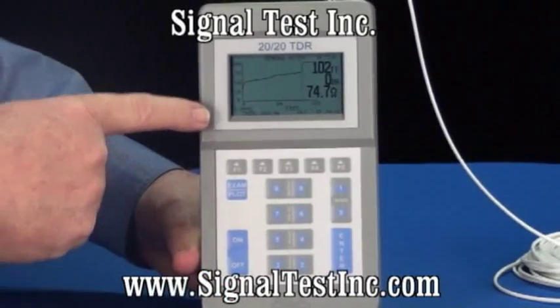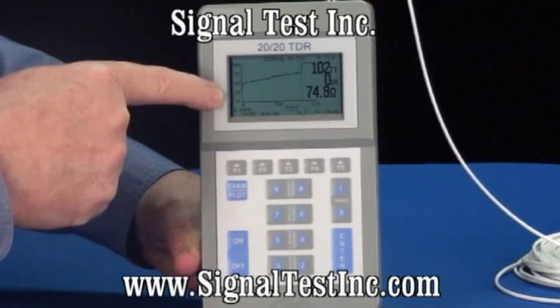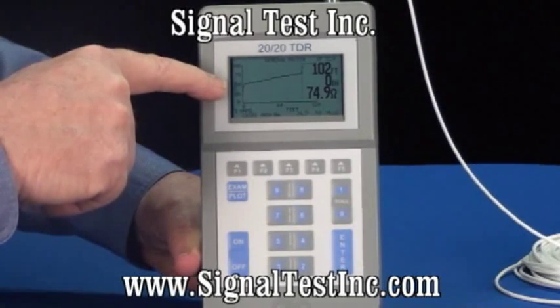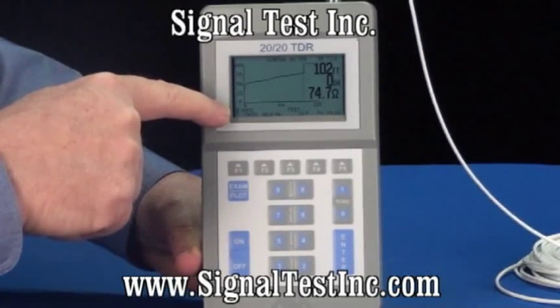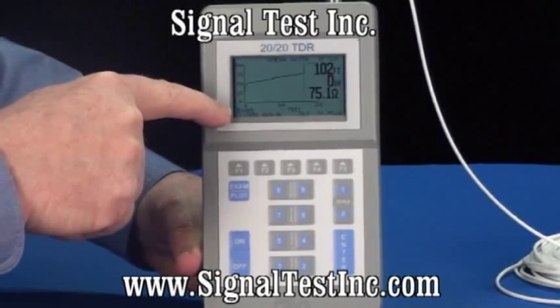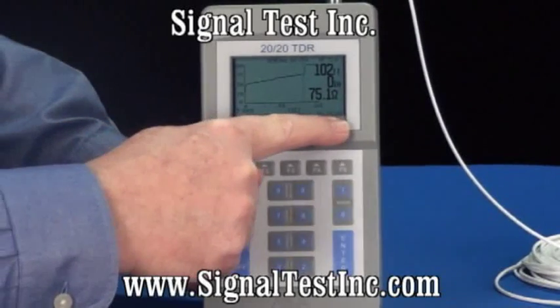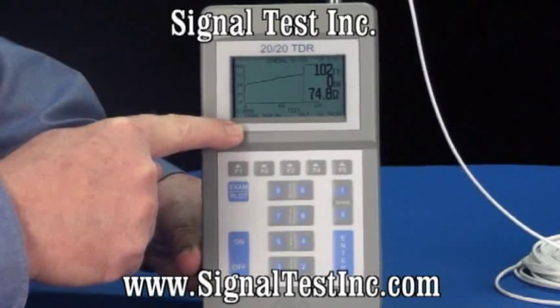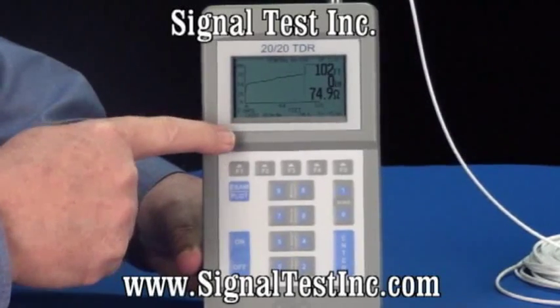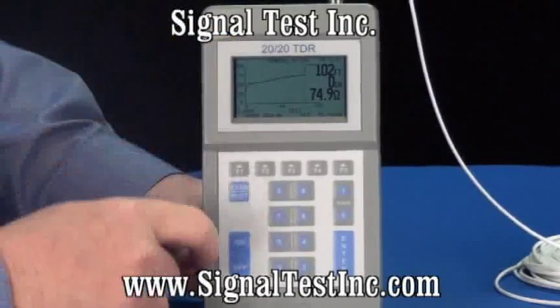Now on the measurement screen we have a scale from 0 to 100 ohms. The cable starts out at 50 ohms and rises slightly with the loop resistance added in, and along the bottom is the length measurement and the cursor information. The cursor is shown at the end of the cable right now where it's open.